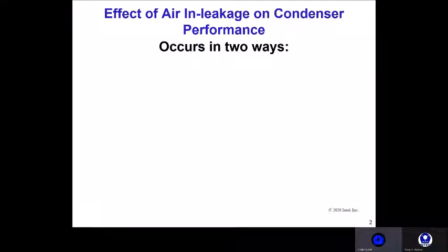The first thing I want to talk about is the effect of air in-leakage on condenser performance. Air in-leakage is an ever-present issue for steam surface condensers, but it does not always cause a reduction in condenser performance or an increase in condenser back pressure.